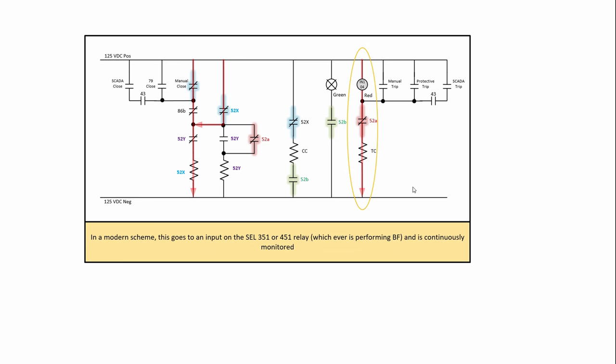So modern schemes will use an input to a relay. We usually have it on a 351 or a 451 where we're checking through the trip coil through that and it's continuously monitored. So it'll alarm even if you're not there.